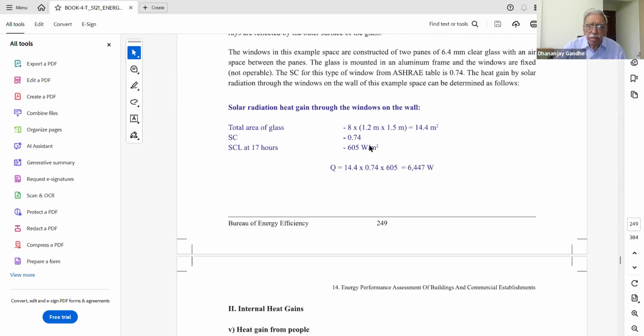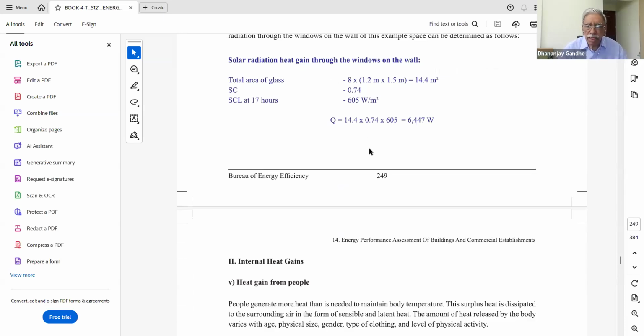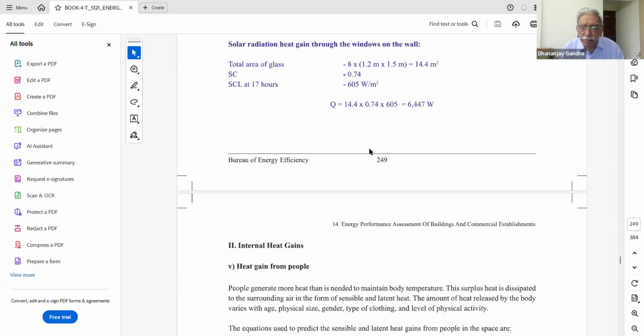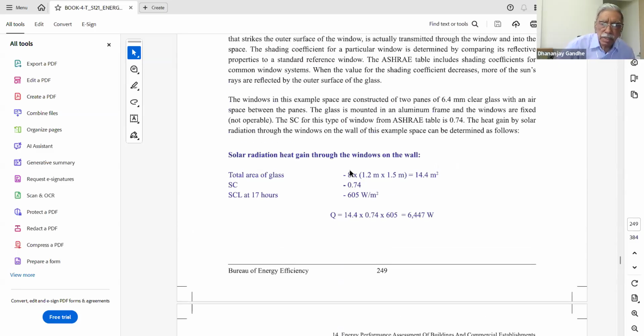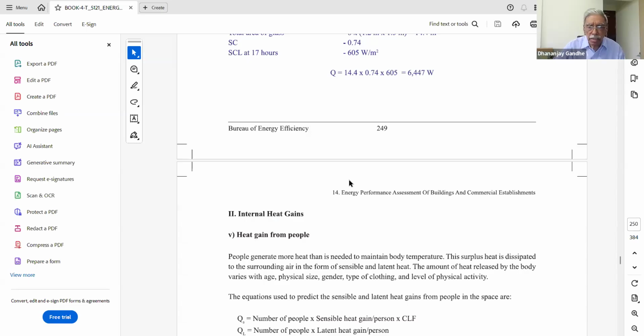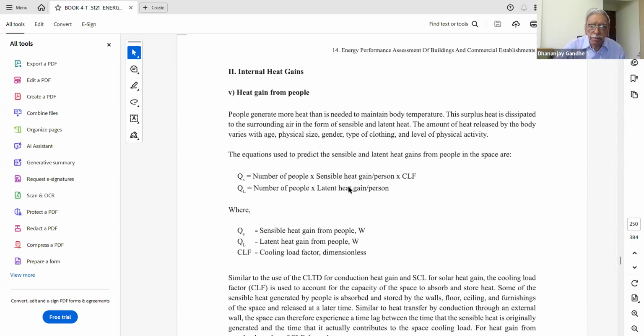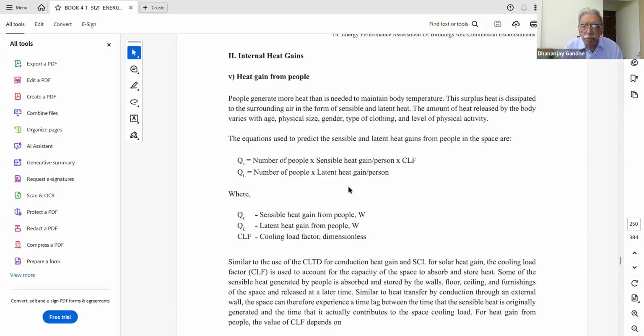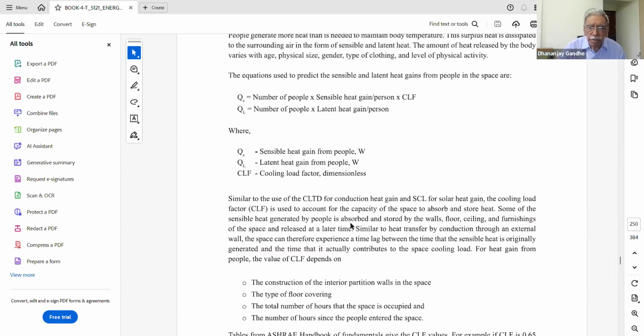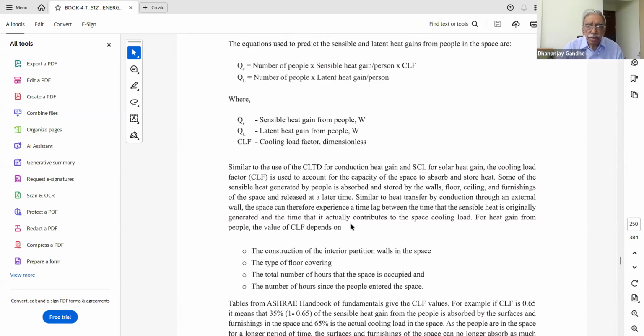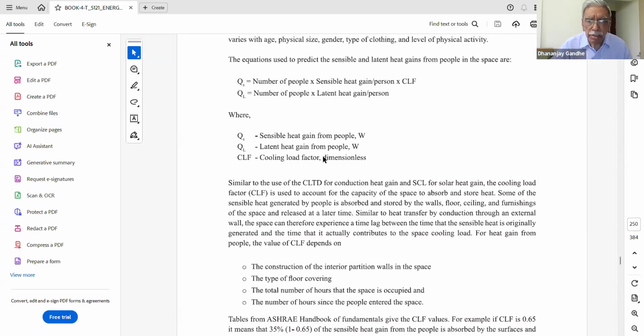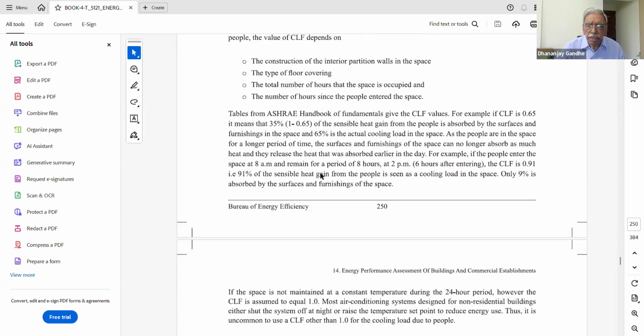Solar radiation is explained over here, and various factors are explained here. I think you can understand. You can go through that if an example is there; you are required to solve some examples. So these are the external heat gains: roof, wall, glass, glass material, etc. And the internal heat gain can be calculated very easily, because knowing the number of people, the heat gain from the people can be known, by knowing the sensible heat per person and the latent heat per person. These values can be taken from the standards and used in the formula mentioned here to calculate the heat gain from the people working in that area.